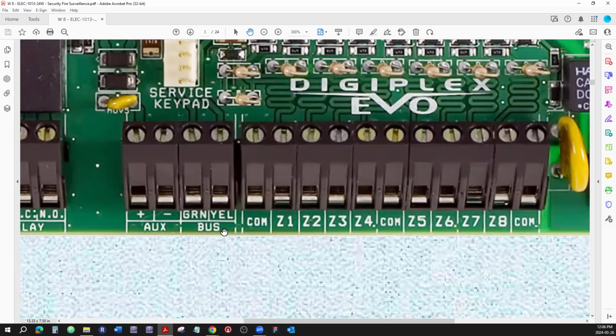Now here is the bus terminal. This is green and yellow because we use—I'll show you those cables later on a few slides further down the road—something called a Z cable, which uses that old color code: red, black, yellow, green. Usually red and black go to the power part, and usually green and yellow go either to a contact signal or are used as a bus communication channel.